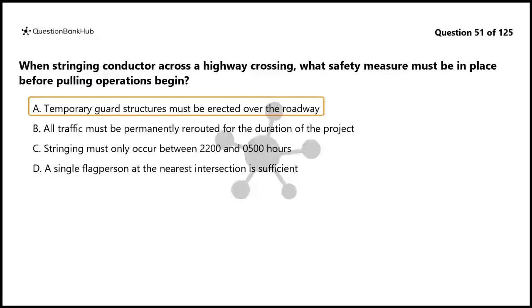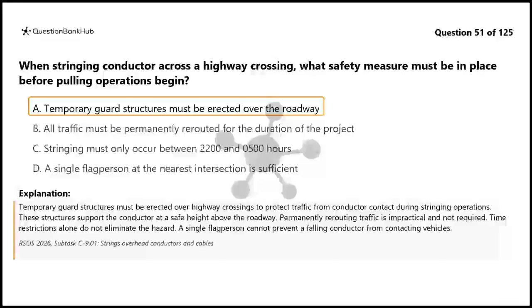The correct answer is A. Temporary guard structures must be erected over highway crossings to protect traffic from conductor contact during stringing operations. These structures support the conductor at a safe height above the roadway. Permanently rerouting traffic is impractical and not required. Time restrictions alone do not eliminate the hazard. A single flag person cannot prevent a falling conductor from contacting vehicles.